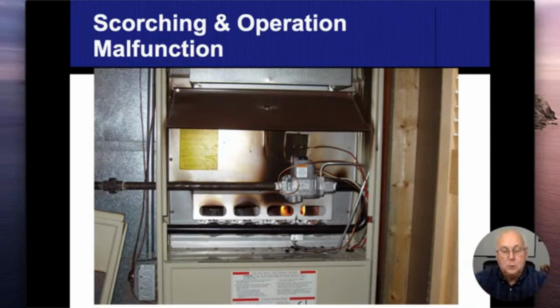Most of our backdrafting is going to occur at the top where the draft hood is, not down here. This is typically going to be flame rollout. But when you have such an isolated spot, it's that particular heat exchanger in that burner that was doing all the damage. You can see how, when fire grows or heat spreads, it goes up and out. So that's what we call the point of origin. And you can follow that V as it comes back in there, and that's going to show where everything is starting from.